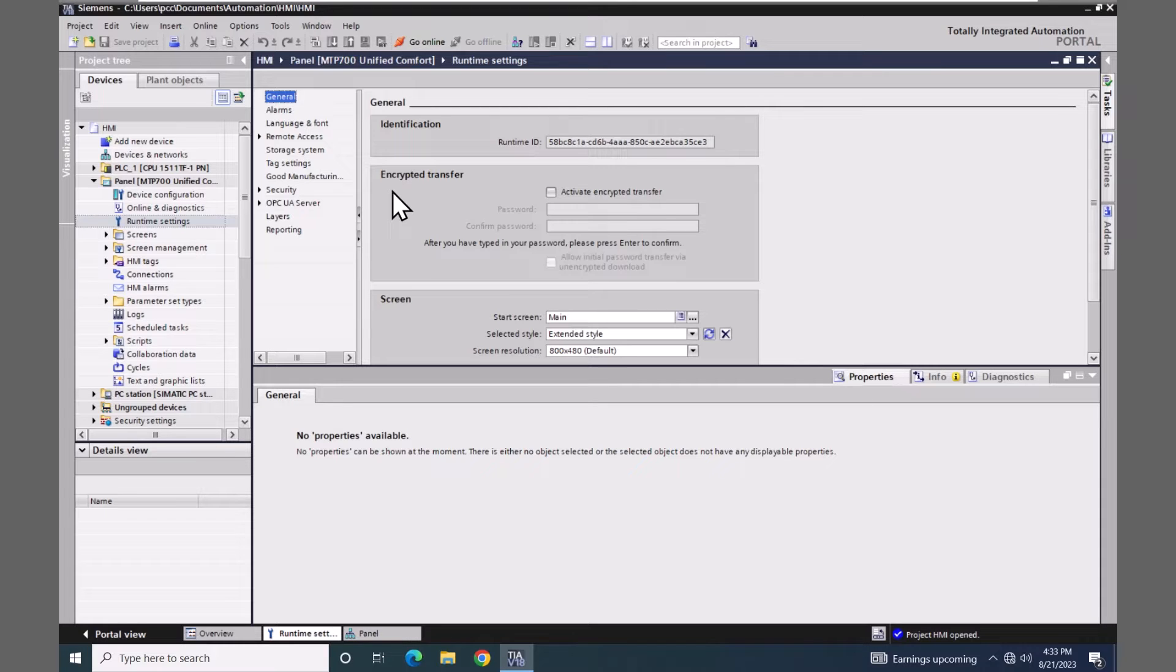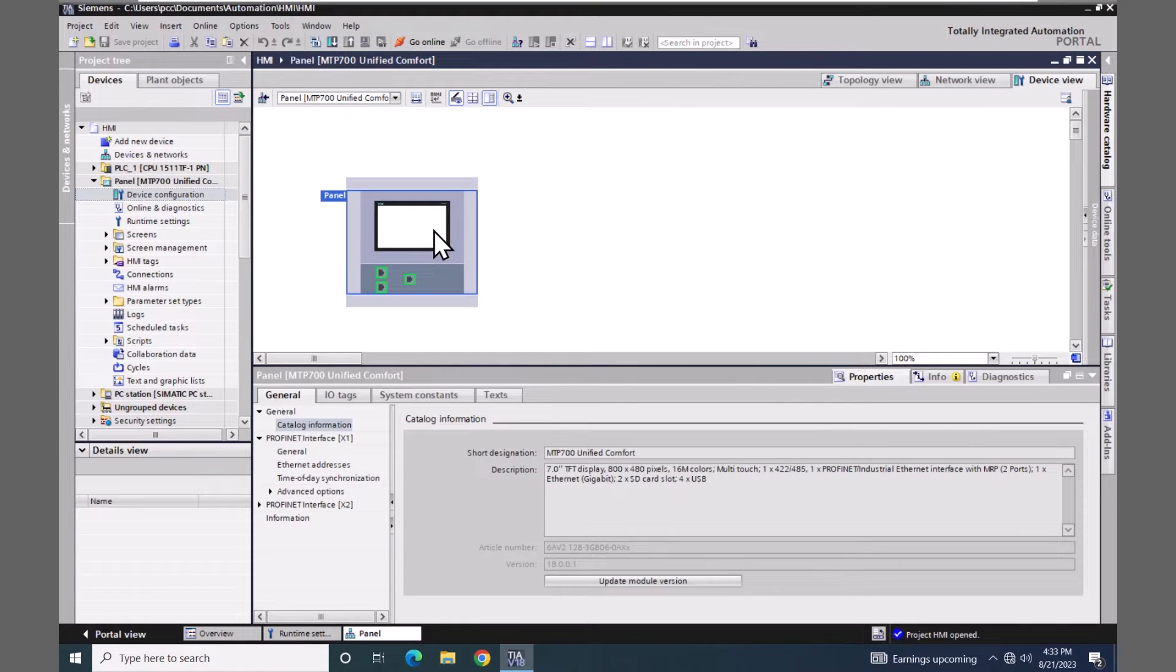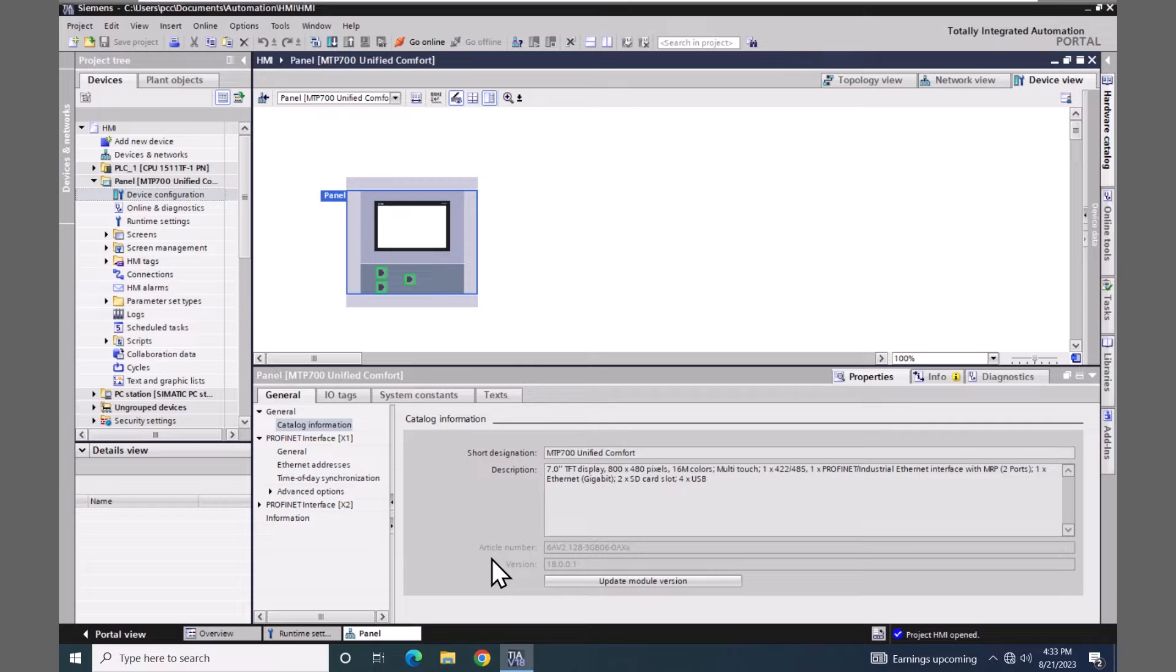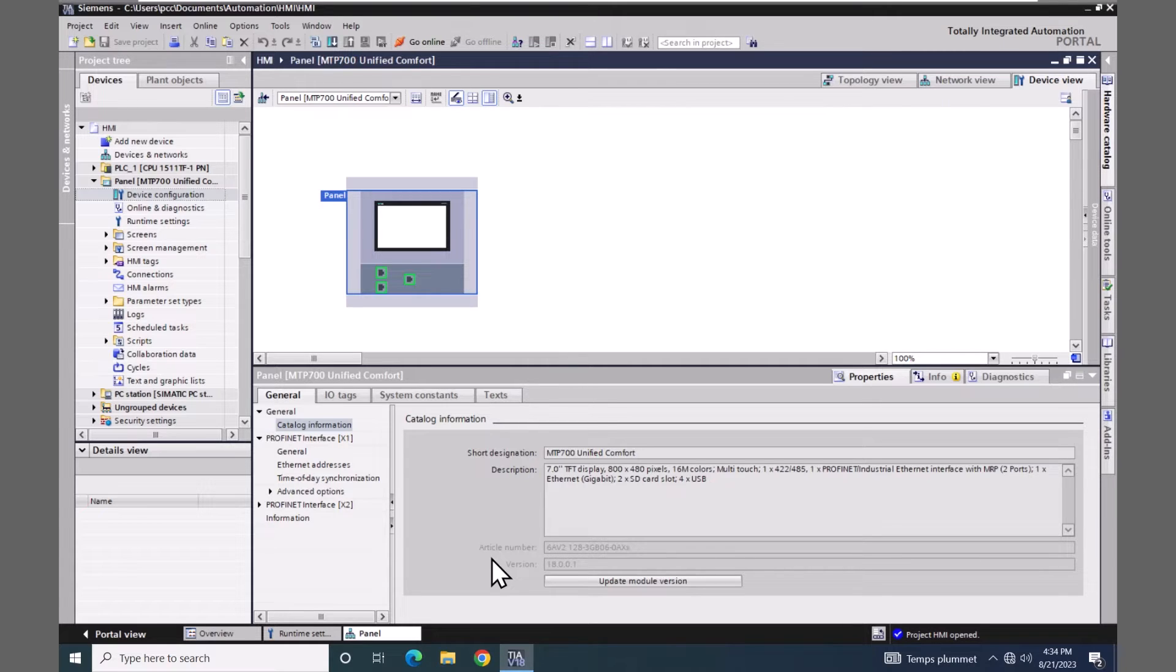Next I'm going to select the device configuration and select the unified comfort panel. Under the catalog information there is a version that is set for the device. This defines the functionality of the panel. I'm using an 18.0.0.1 image, so I can load this into that image version or greater on a unified comfort panel. If my device version here was configured to a newer version than what's actually installed on the panel, you would have to go through the process of updating the operating system on the panel to bring it up to at least this device version.